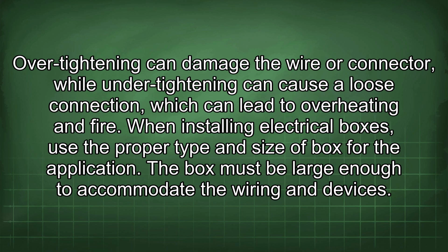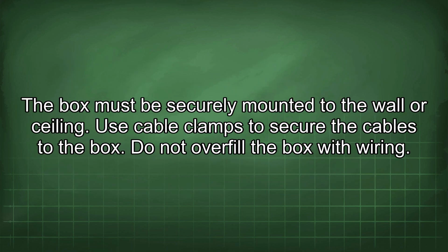When installing electrical boxes, use the proper type and size of box for the application. The box must be large enough to accommodate the wiring and devices. The box must be securely mounted to the wall or ceiling. Use cable clamps to secure the cables to the box. Do not overfill the box with wiring.